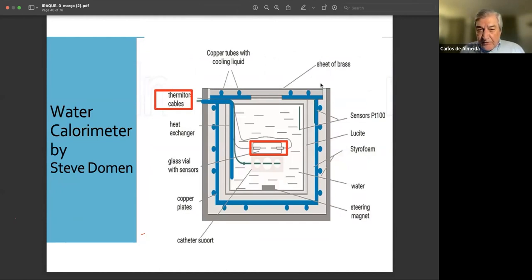And what you see here is a water tank. Inside of the water tank, we have these two temperature sensors. You have a sheet of brass on the top, and you have a styrofoam here to isolate this water from the room. And then you have a stirring magnet to make this water revolve. And also you have the glass vial sensors, which is where you place the thermistors. And those thermistors are calibrated by the national physical labs in each one of these countries. So this is an enormous amount of work. To set up this calorimeter takes a few hours.